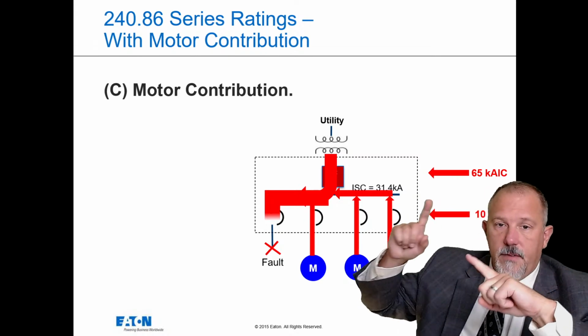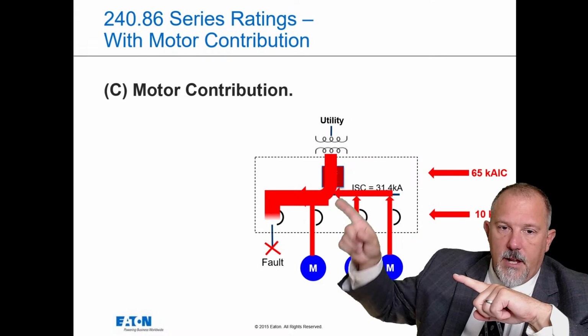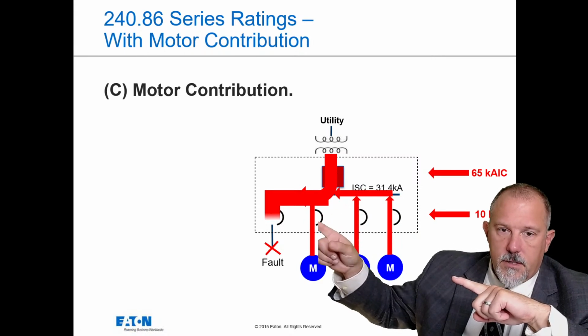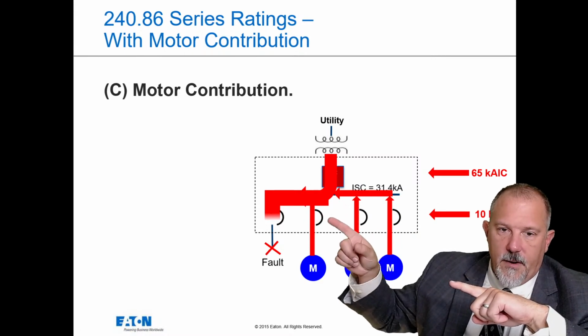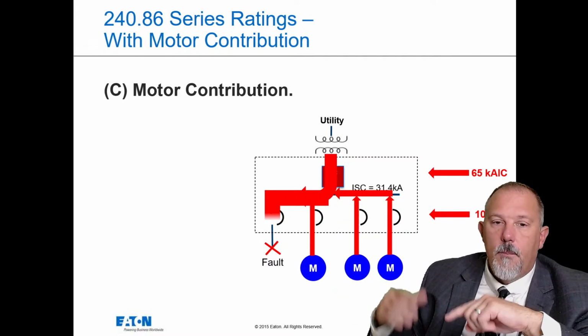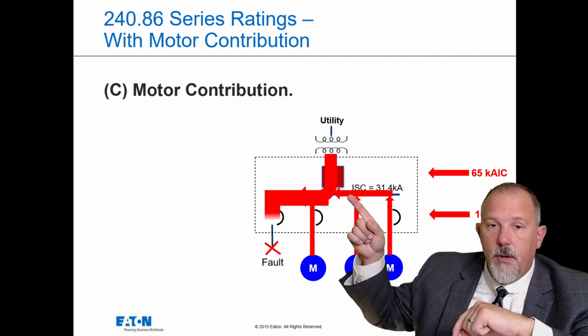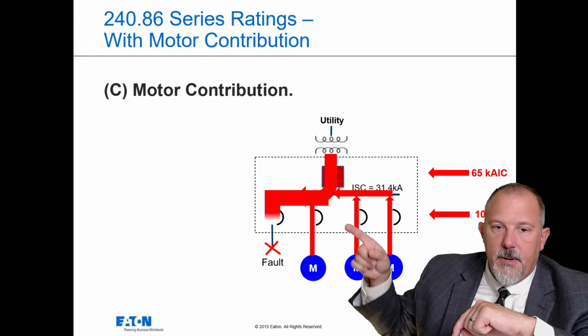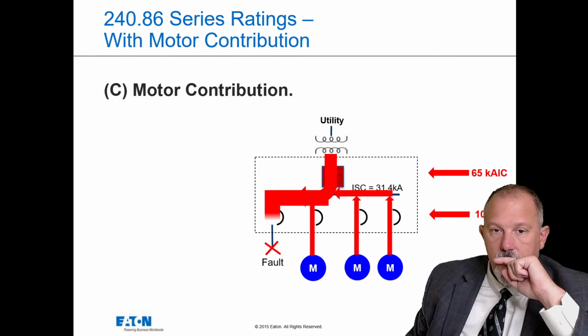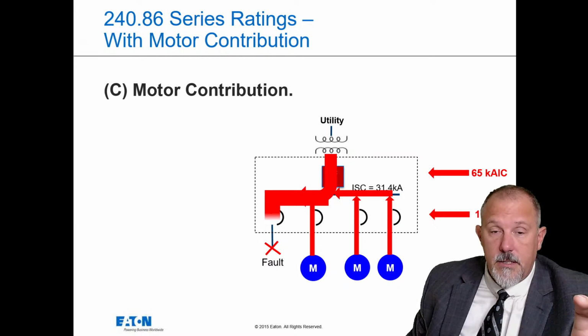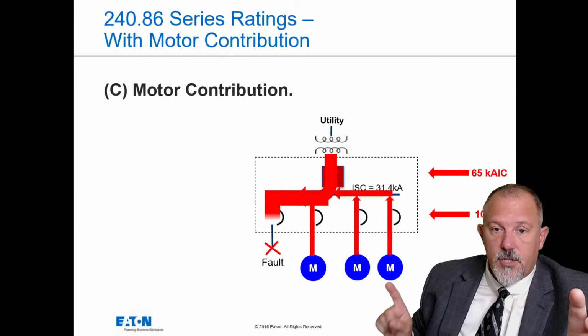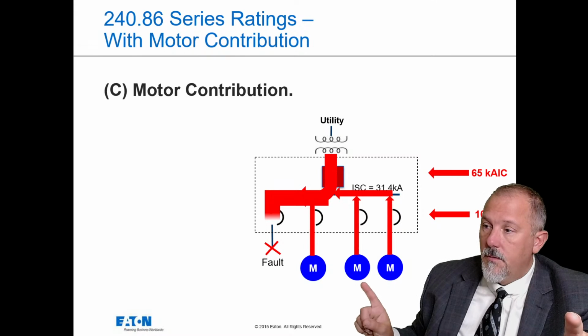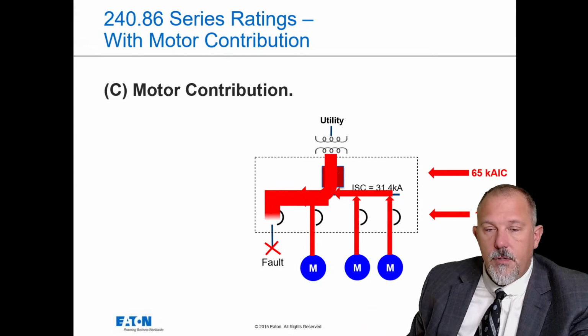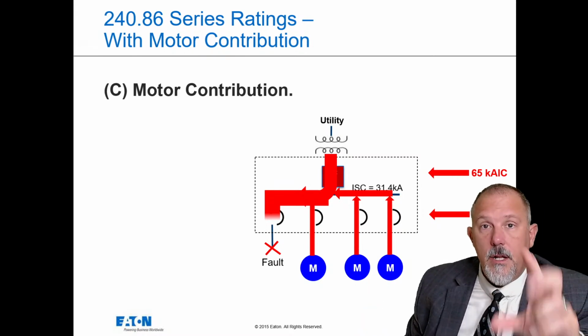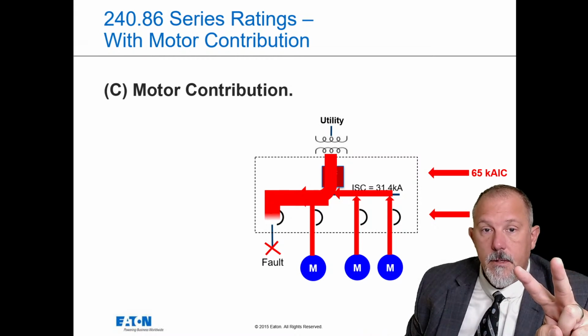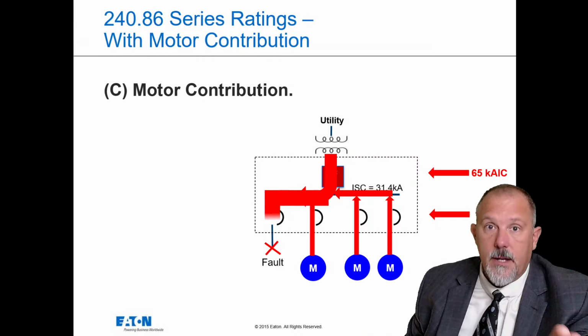Remember, I've got two devices. I've got this main device up here, and I've got that device down there. This, not the one that's right here in front of my finger, on the other side, down, that's upstream of the fault. So that device and the device that's above where that fault is are the two devices that I need to series rate. The motors that are here, these motors, contribute the fault current that is in between those two devices. That's what we're talking about.